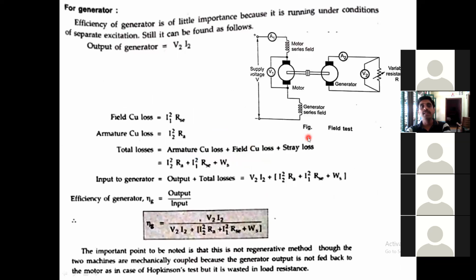If you take the generator, generator efficiency is not a big issue here, but if it is required you can calculate it. For a generator, the electrical output can be calculated. For a motor, the electrical input can be calculated. For a generator, the input cannot be determined directly, and for a motor, the output cannot be determined directly. You have to convert those values in terms of losses. So the output of the generator is V2 I2.